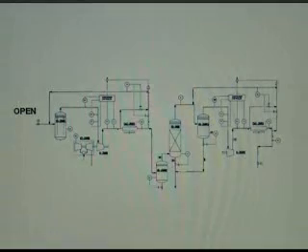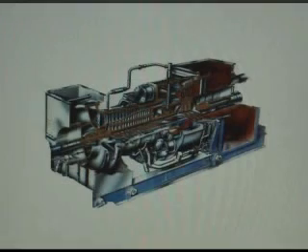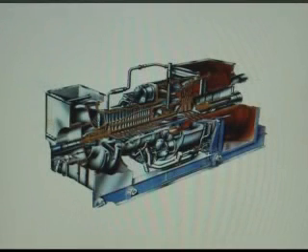And it held them there for a long time because you don't see them here, but there's vents off the flare that were open so that the process loop would never build up any pressure, so the gas was happy to stream right through and then back out the flare. So he was pinned inside, this thing's spinning at 1,500, 2,000 RPM, and he can't move.